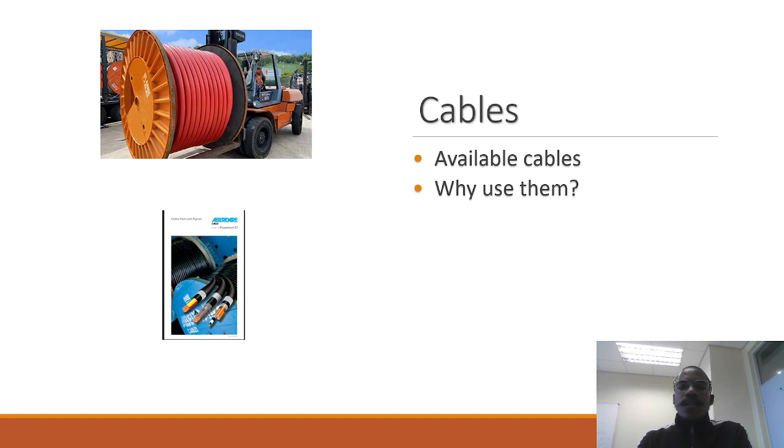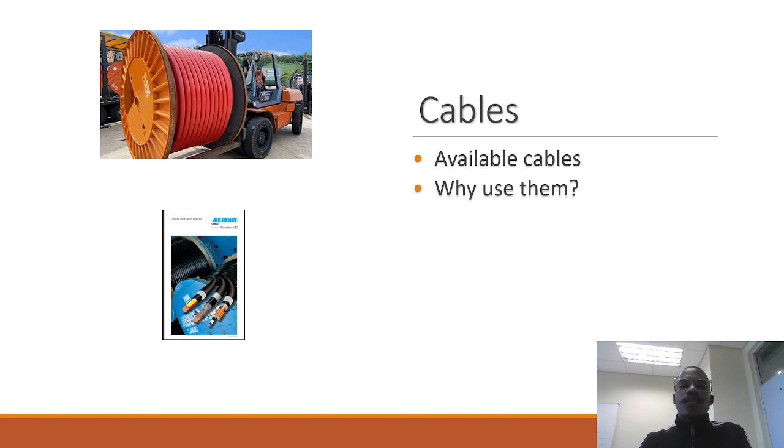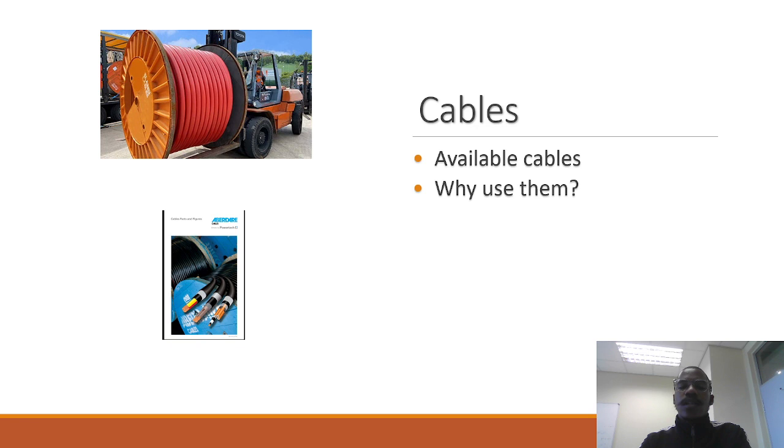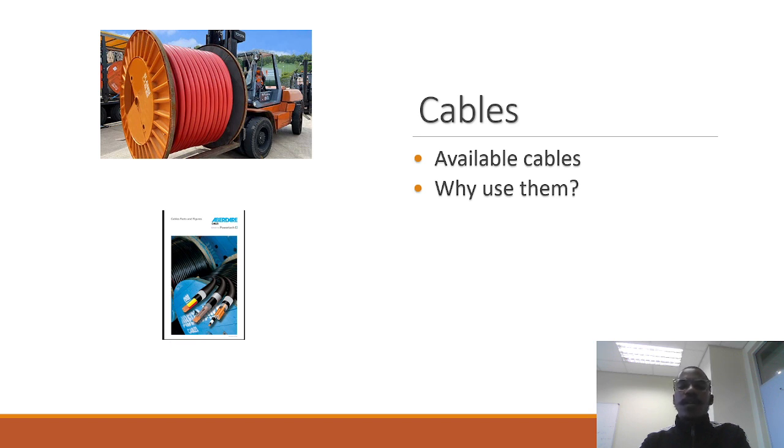Different town councils and different clients require specific cables, but for us we are mainly going to look at cables because we will be talking about voltage drops. With that we need to use different cabling sizing because resistance is equal to rho times L over the area. When you increase the area it decreases the resistance within that cable, so you can get more electrons flowing through that cable.